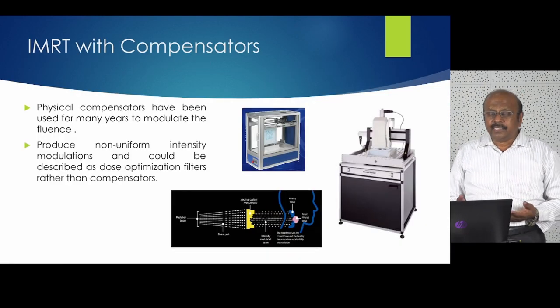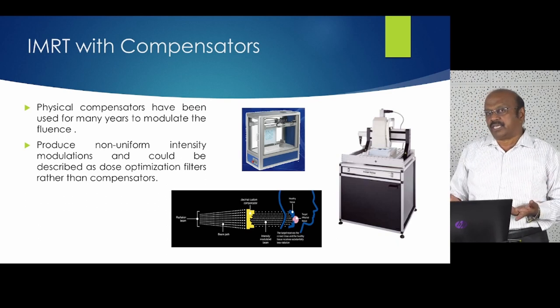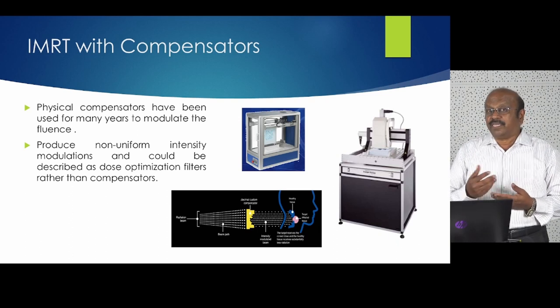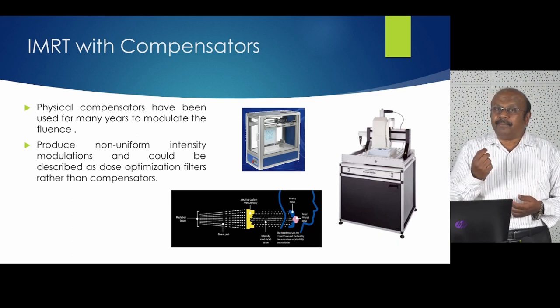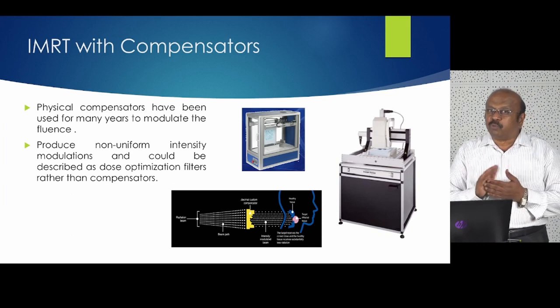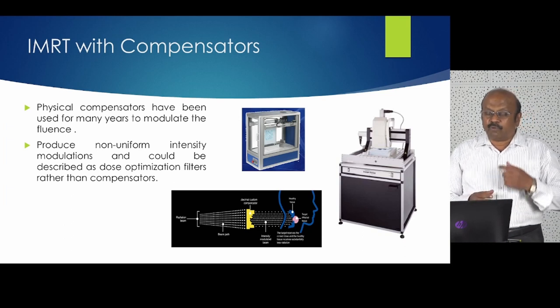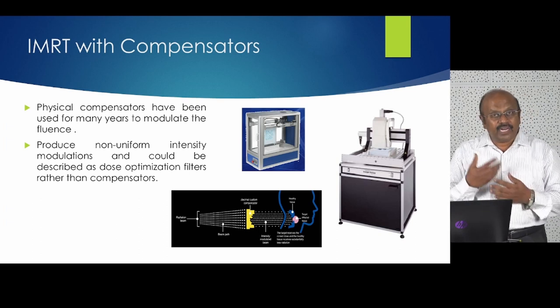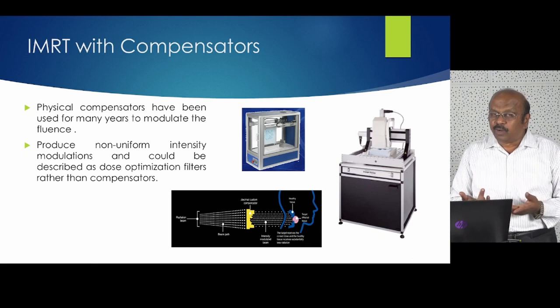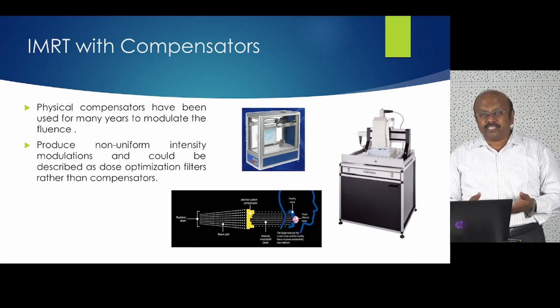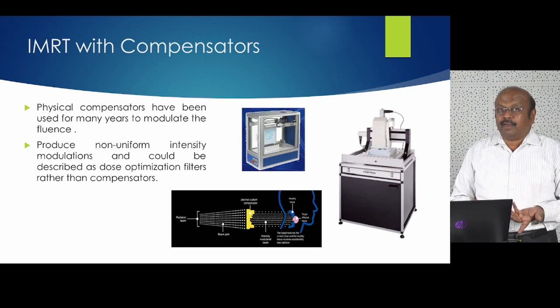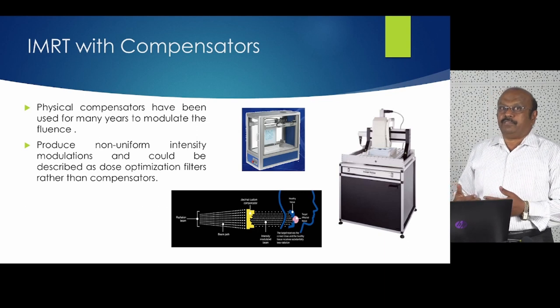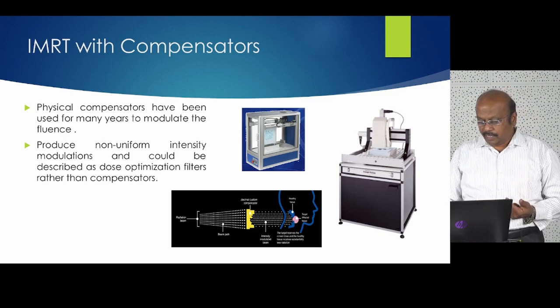When you use a compensator, you physically have to make one per beam — for a 7-beam IMRT, you make 7 compensators. The advantage is you don't worry about beamlet size and can make it very smooth. But the disadvantages are many: you must make one for each field, replace the correct compensator for each field, find storage for all days of treatment, and reuse them regularly. Multi-leaf collimator-based delivery is much more convenient.